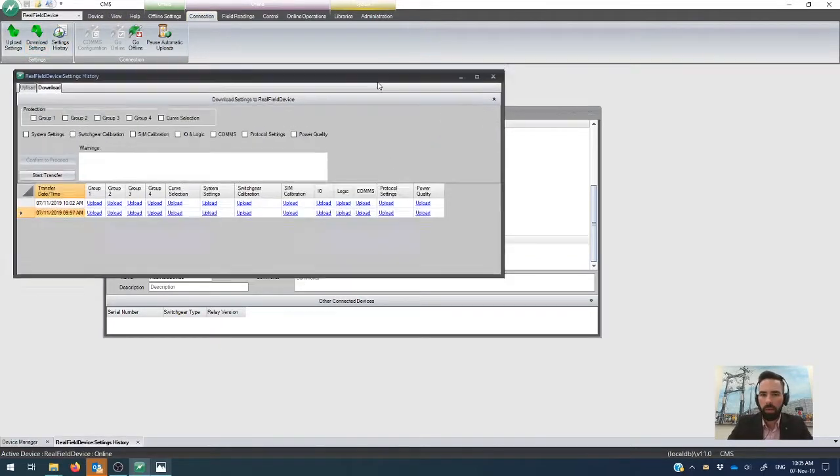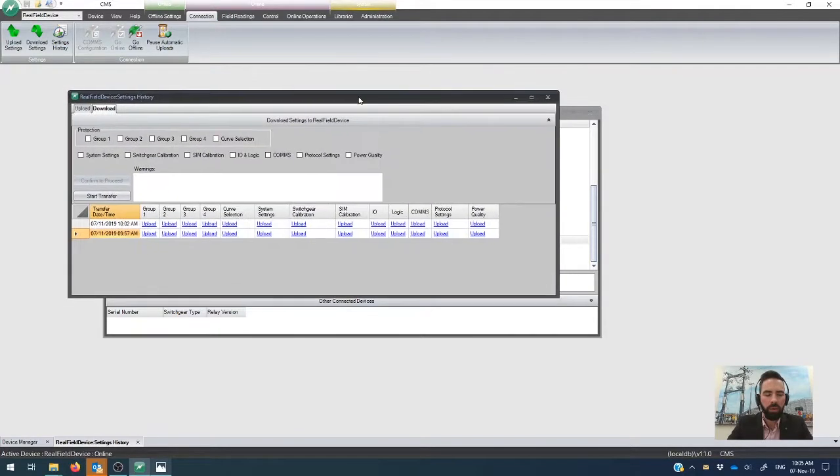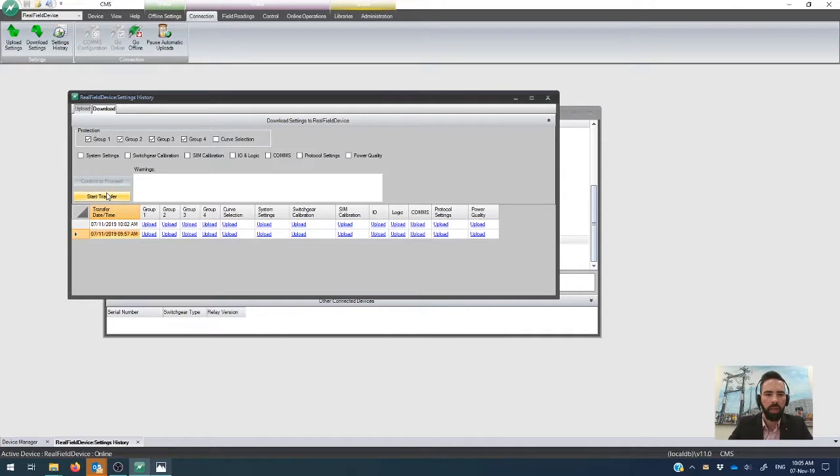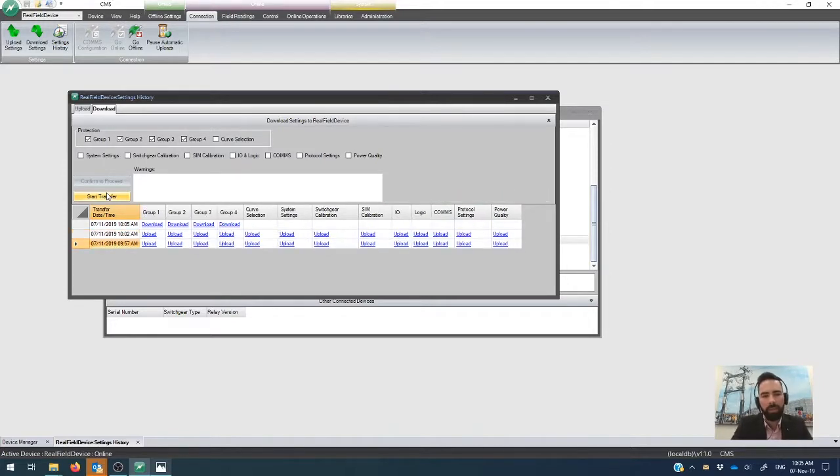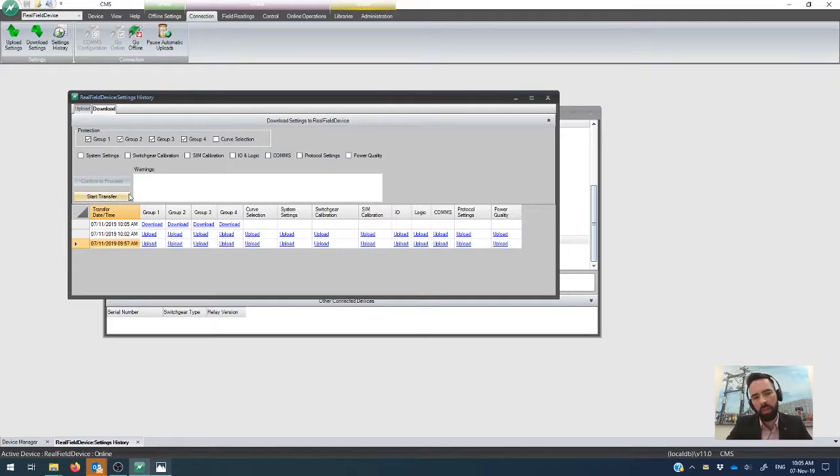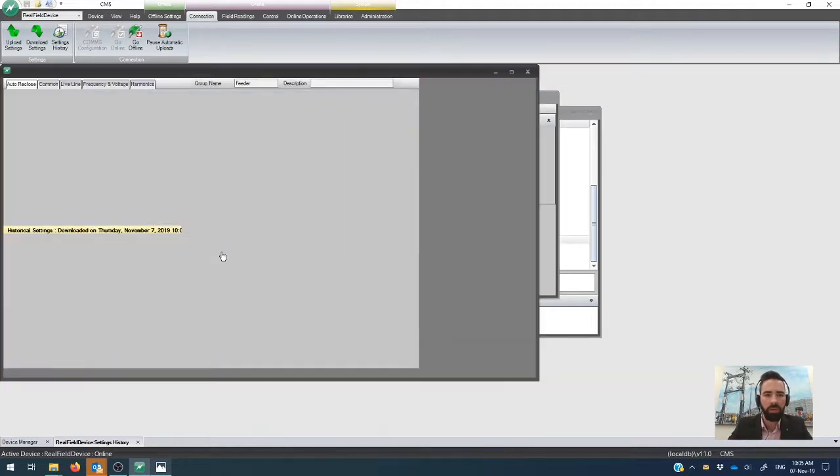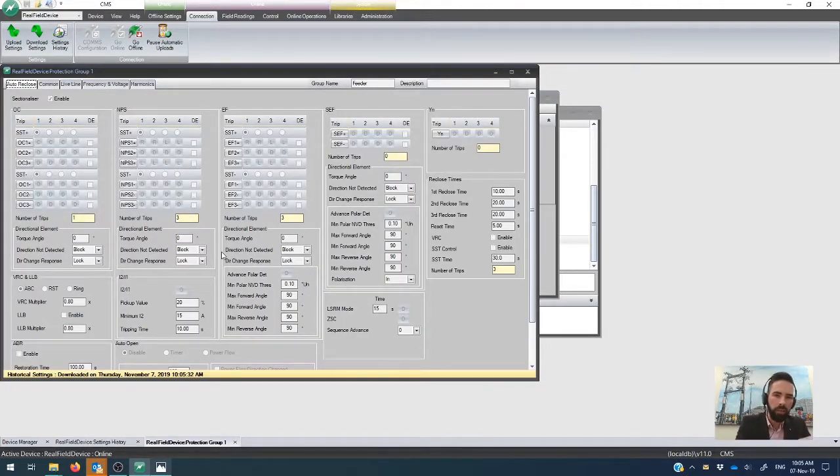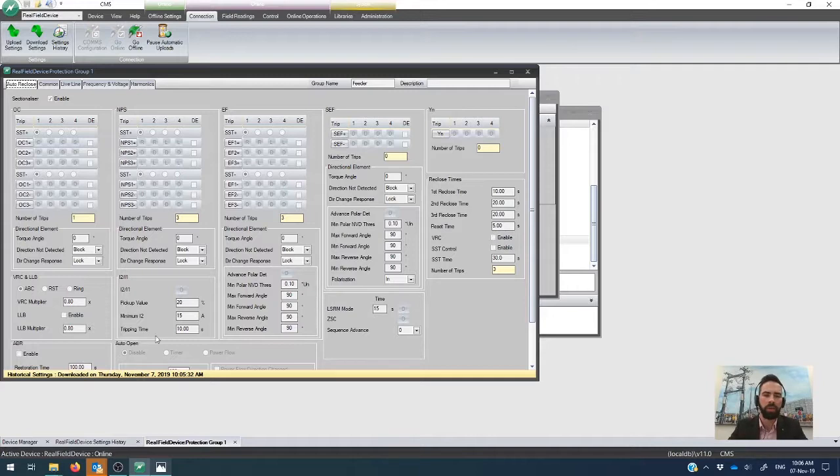When you download the settings, this time around, it's a little bit different because what you can do is you can select the settings that you want to push through into the device. So I'm taking those guys there, and I'm going to start the transfer. So I'm pushing the new group settings that I've made the changes to into the relay. All right. But at the same time as pushing them into the relay, CMS is creating a copy, a snapshot of what that data transfer looked like and saving it in this settings history, which are these guys over here. So if I open any of those individually, this is not a direct link to the relay, but it is a copy of what you downloaded into the relay at that time. So you'll see, again, historical settings.